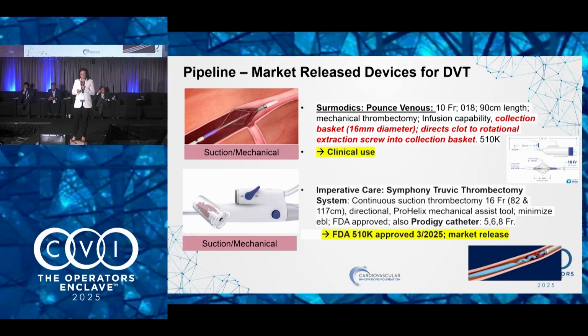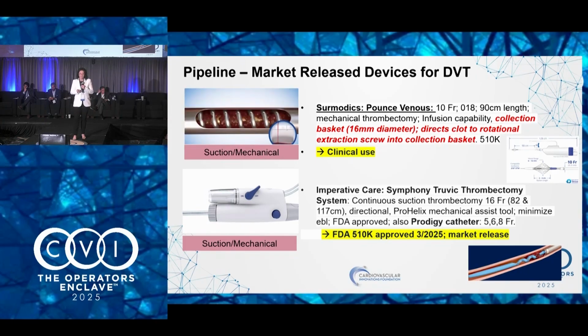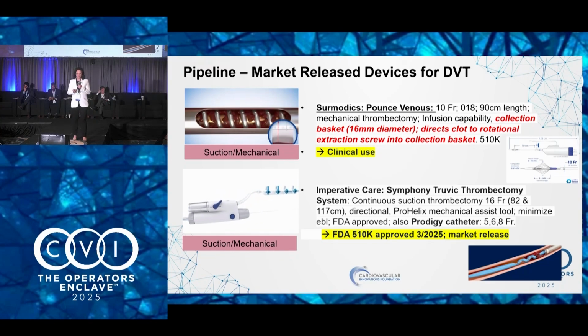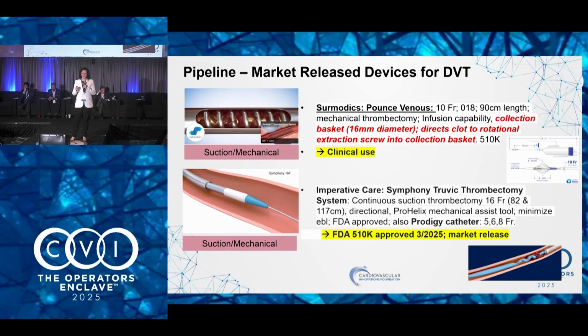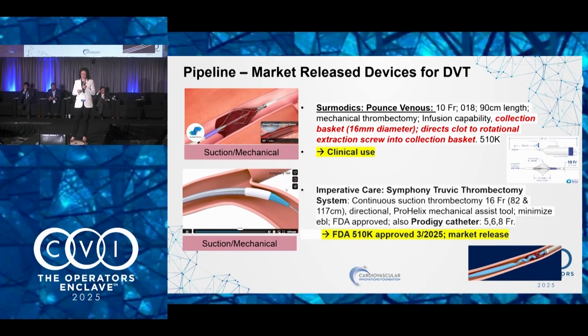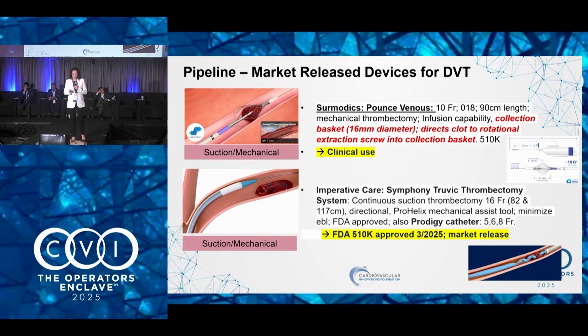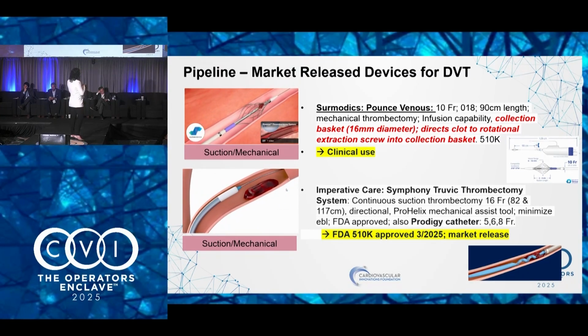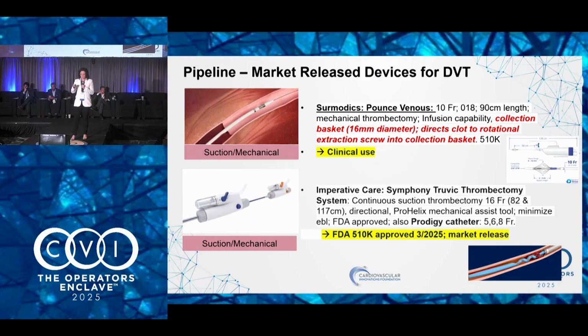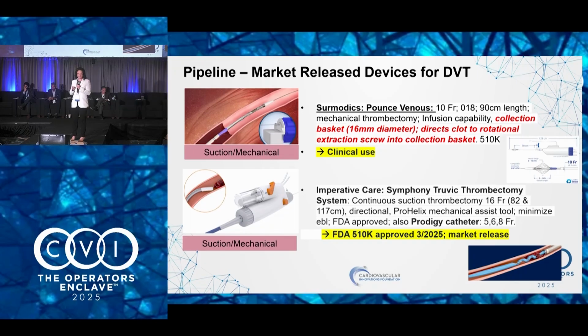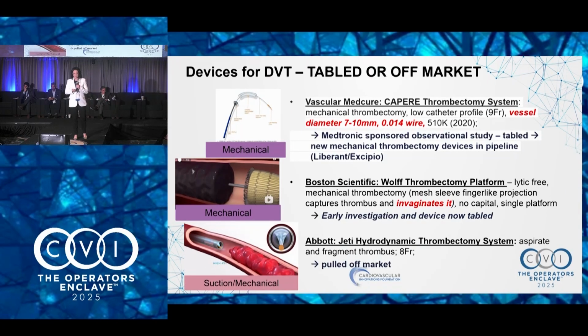The one to receive the most recent 510K approval and already in the market is Imperative Care's Truvic thrombectomy device. It's a continuous suction and mechanical device. It's directional, so you can direct the catheter to the specific location, and it uses this ProHelix mechanical assist device here at the bottom to bring in varied-age thrombi and extract them into this small container on the back end, and that helps to minimize the amount of blood loss. So we'll see where these devices land in the space.